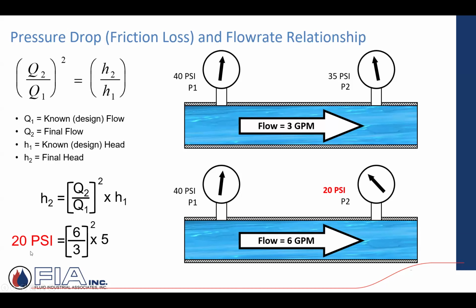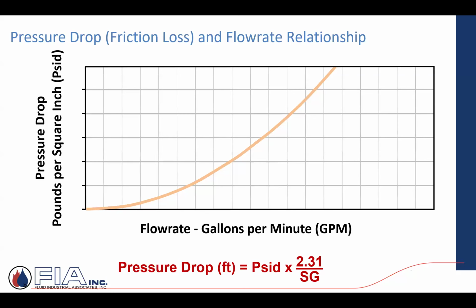Conversely, go the other way. 3 gallons a minute, cut it to 1.5. The pressure drop doesn't drop from 5 to 2.5. It goes to 1.25. So now you start getting into variable speed pumping and energy requirements and horsepower and kW savings as you get into big systems. So that's pressure drop, friction loss, and flow rate relationship.